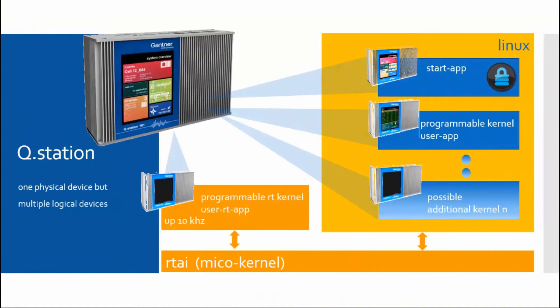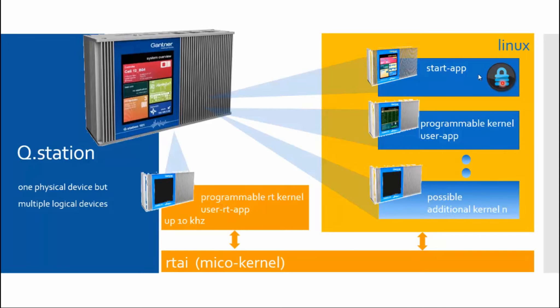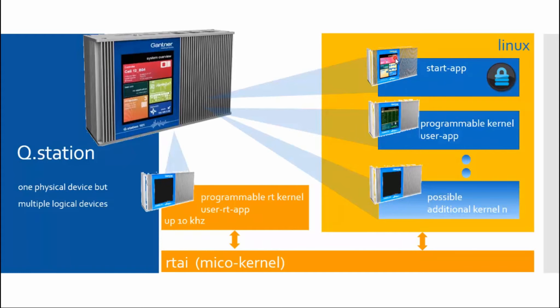That was this device that was found, and this is the real-time kernel. What was also found is this device. It is a Linux process and a micro-kernel process. What wasn't found is the process for the startup, but that is hidden for the user on purpose, so they cannot change the programming of the startup. What was also not found are other kernels, as they are not set up on standard controllers. Theoretically, there are several kernels, which means in one Q.station there are logically several devices, and at least or at the moment there are three: the start app, a programmable user kernel within Linux, and a real-time kernel, which is called directly as real-time task within the micro-kernel.